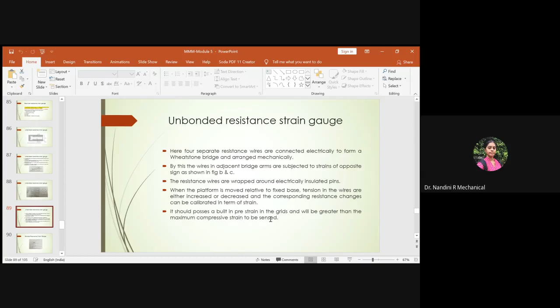One thing you have to keep in mind: the device which has been developed as an unbonded resistance strain gauge will have a built-in pre-strain value around the grids, which is of negligible value and will be greater than the maximum compressive strain to be sensed. So this is about the unbonded resistance strain gauge. The first classification we have dealt with. Then we come to the next: what do you mean by a bonded type of strain gauge?